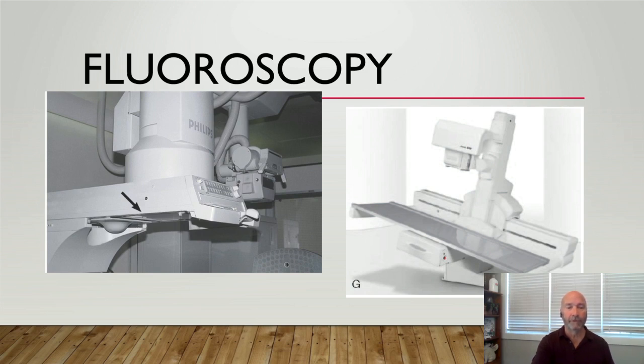You need to be real careful when you're in clinicals that if you have what we refer to as an RF room, that is radiography and fluoroscopy, that before you start moving this thing around, because it's very heavy, that you get this out of the way. This does not look like a good position for it. Being a two-dimensional image, I can't tell how far away that is. That might be the perfect place for it. But in a lot of cases, in a lot of x-ray rooms, this can get in the way of that. And if you tilt the table up, you can do some damage to that, or you can run the fluoro tower into it and do some damage to it as well.